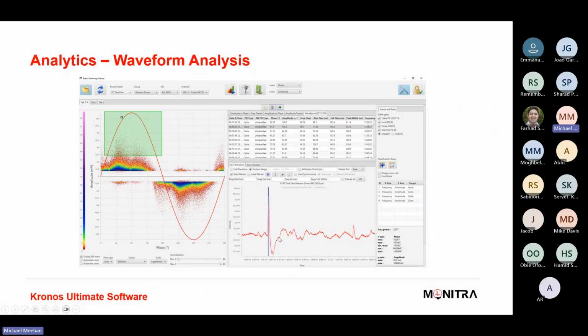So when we analyze these pulses, we can run machine learning on these million plus data points and remove any which are not PD-like. You could have noise which could be in some ways like PD, and we don't want that to interfere with the way that we analyze and measure. So we can run machine learning on these vast data sets and end up with some very accurate and concise reports. And the big benefit there is when you do multiple tests, or you're looking at multiple data sets time after time, those rules that you set and that data that you're looking at, you get real consistency and continuity in the way that things are analyzed.